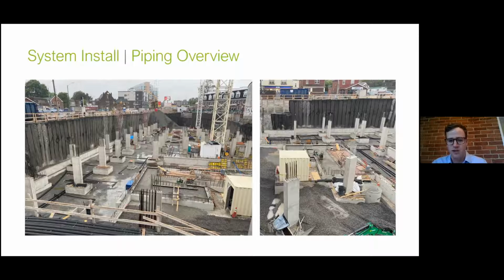Based on recommendations from the geothermal designer and our local building sciences engineer, we needed to establish a clear lift about 18 inches above all of our piping runs before we were able to drive heavy pieces of equipment in. So that was a lot of really detailed, slow, careful backfill around all this piping to establish that. Before we get into that, all the piping is pressure tested.